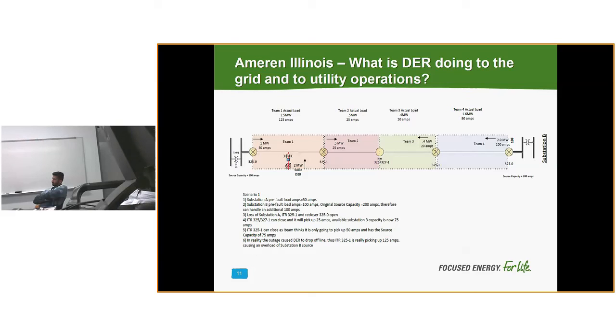If I lose substation A, if I lose this source here, just like we talked about, 325-1 and 325-0, this one and this one, will open, sectionalizing this side. The normal open one in the middle can close and pick up the 25 amps that we've got on this section. So far, so good, right? Because I had an additional capacity of 100, I can pick up 25 easily. How much capacity do I have remaining after I pick up this section? 75. Yep. 100 is how much I can handle, I just picked up 25, so I have 75 amps that I can still handle from A if I wanted to pick up here. Make sense so far? Okay.